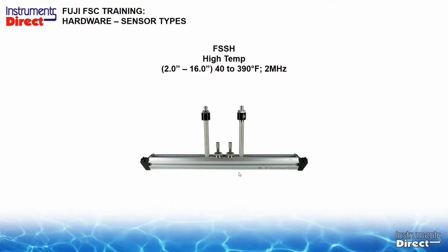One transducer we haven't mentioned is the high temperature version, the FSSH. This is up to 390 degrees F. The traditional transducers from Fuji go up to 212 degrees F. This goes only from pipe sizes 2 to 16 inches. It's a 2 megahertz transducer, but it is very big and bulky. You can see the thermal rods that come on the top of the device are large, so you need to have a big suitcase. And the second biggest problem is, you guessed it, the price. This high temperature sensor costs almost as much as the handheld meter itself. It comes in at about 5,000 bucks just for the high temperature transducer. So that is kind of interesting as opposed to the other transducers.